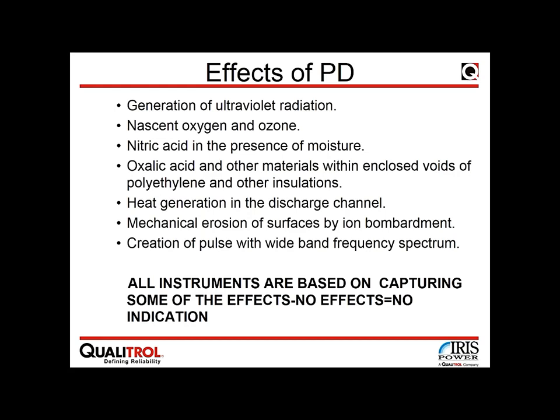Partial discharge cannot be measured directly — it must be measured through its effects. Seven effects exist; most instruments rely on the creation of a pulse with a wide-band frequency spectrum. Other instruments use optical recognition or ozone detection in air-cooled machines. Capturing these effects indicates the presence of partial discharge; without them it is very difficult to confirm whether PD is happening inside the machine.